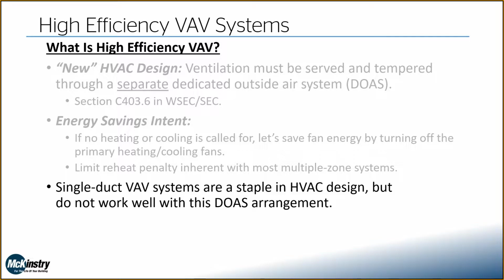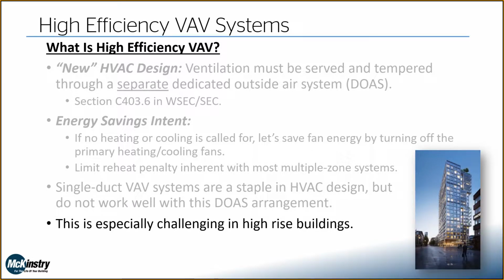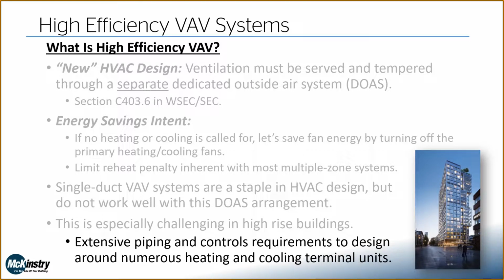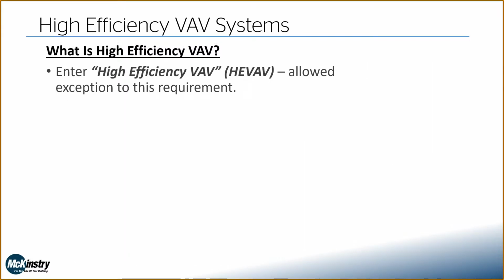So talking about single duct VAV, we've been doing single duct VAV forever. I mean, we see it everywhere. It is a pretty efficient system, but the general setup of a single duct VAV system doesn't work well with this whole separation of ventilation air from the heating and cooling systems. And in high-rise buildings especially, this can be problematic. You think if you have 40 stories that you have to run your HVAC through, that's a lot of piping, a lot of controls. It's not very practical for that type of application. So we have this high efficiency VAV, HEVAV, which is an allowed exception to this requirement.